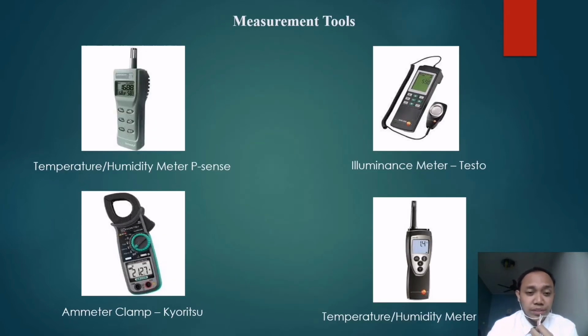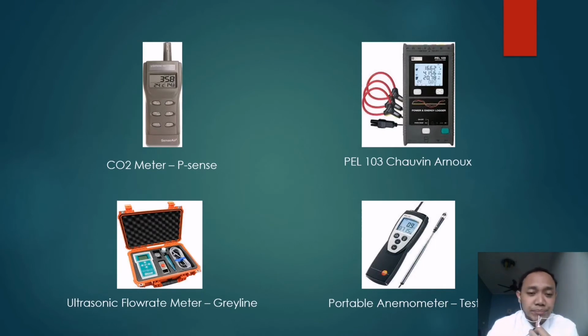Okay, these are the measurement tools. First is a temperature or humidity meter to measure the temperature of the area. Next is the illuminance meter to measure the light intensity in a certain area. The ammeter clamp measures current at an electrical panel such as an AHU electrical panel or chiller electrical panel. Next is the carbon dioxide meter, CO2 meter, to measure the carbon dioxide in a certain room. PEL, the power energy logger, is used to measure power and energy for all the electrical installation.